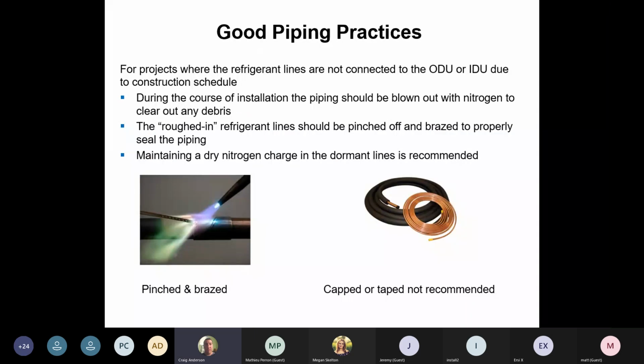So, good practice for piping as well. A lot of guys do a lot of new construction. They get their install crew out there, slam in 6 units, and then they go back and install the air conditioner outside. Like we talked about before, we're dealing with 3/8 lines, 1/4 inch lines. Any blockage in those lines could do a lot of damage to the air conditioner, and it could do a lot of hunting. What I mean by hunting is your air conditioner's refrigerant is going to hunt for different flows if we're working with TX valves and stuff like that. So any little bit of dirt that gets in our strainers or screens could throw the whole game off for you if you're out there servicing.